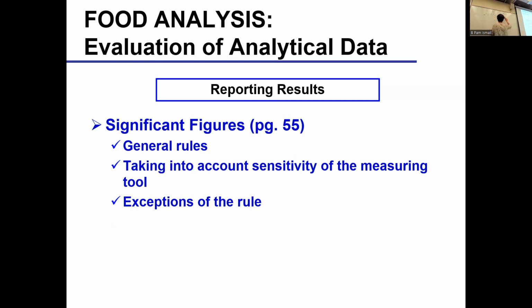So it's accurate to this far. Sorry, milliliters, not microliters. We're talking milliliters. So it's accurate to, if I put 50, it's either 50.05 when I reach out to here, or it is 49.95 milliliter in this range. So I added a level of accuracy.